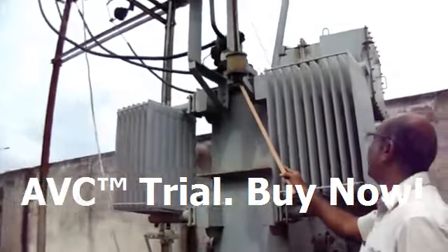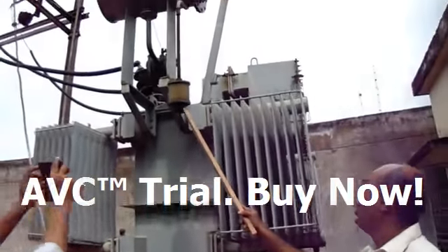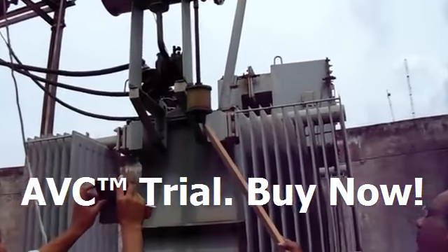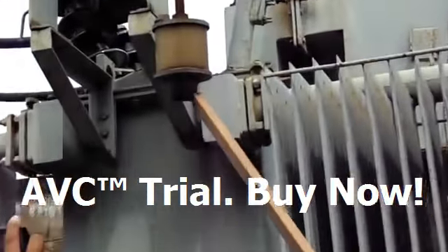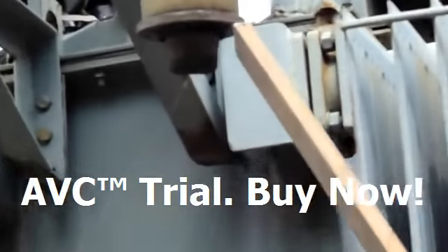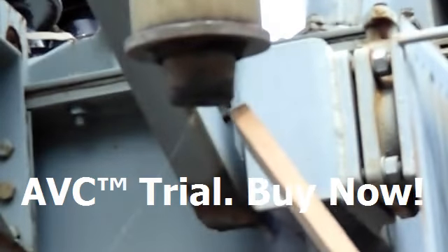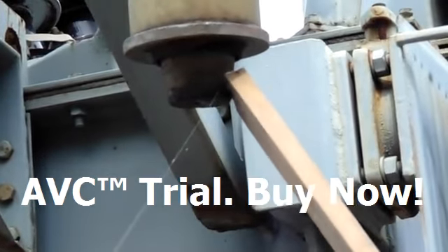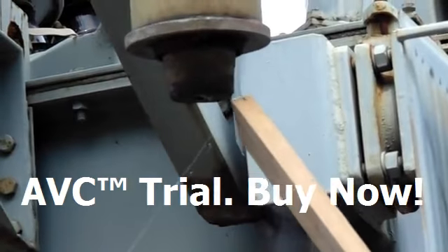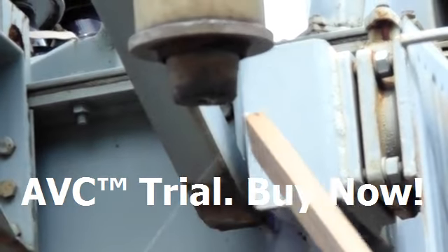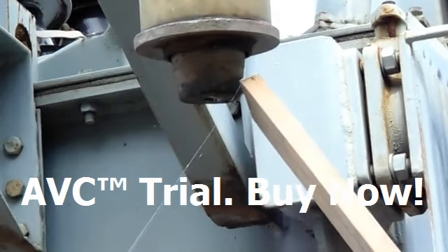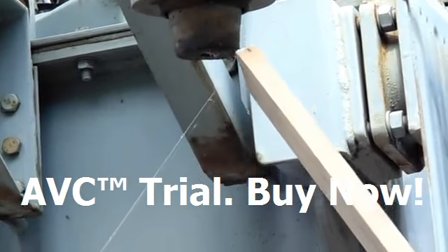So here there is an oil seal. There is an oil seal you can see at the bottom. Whenever the air breathes in, there will be suspended particles with the air. Suppose some dust and all these microfine particles will be there, that will get suspended in the oil. So therefore this acts as the oil seal, and this is also an important part. Whenever you do the maintenance, you remove this and see whether the oil in this has deteriorated or been damaged. Replace that oil with fresh oil.